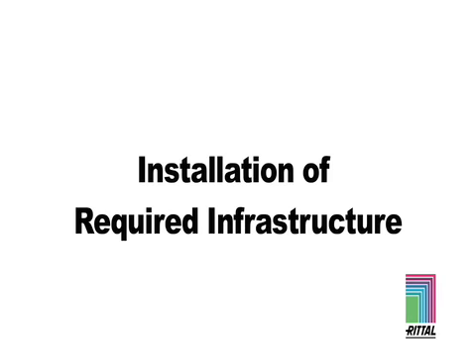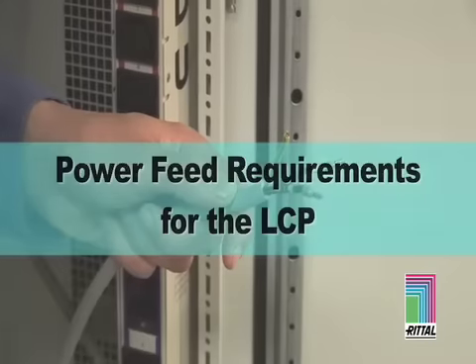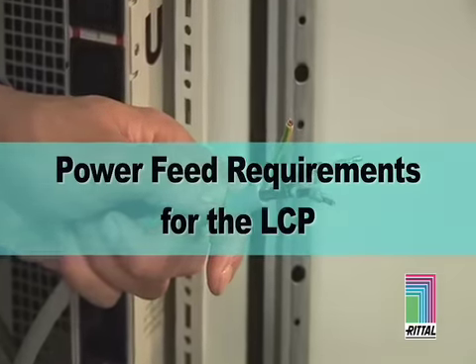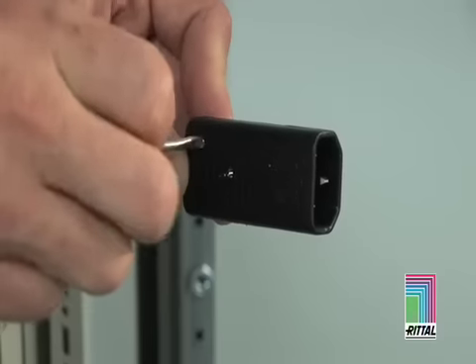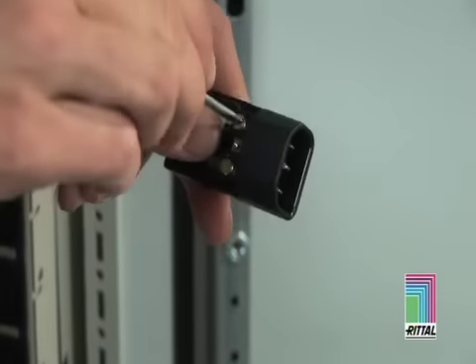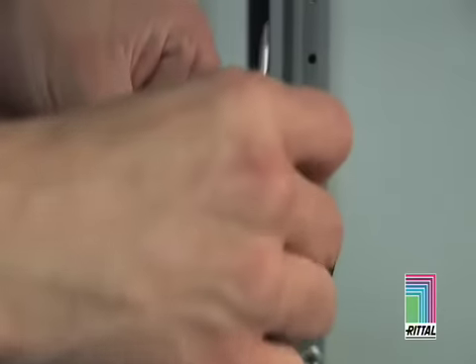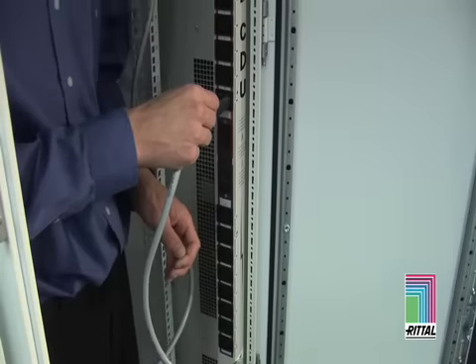Installation of required infrastructure. Power feed requirements for the LCP. Typically, the LCP is hardwired to a 208, 230 volt electrical source by an on-site electrician. Installation of standard power connections are completed normally in the field.